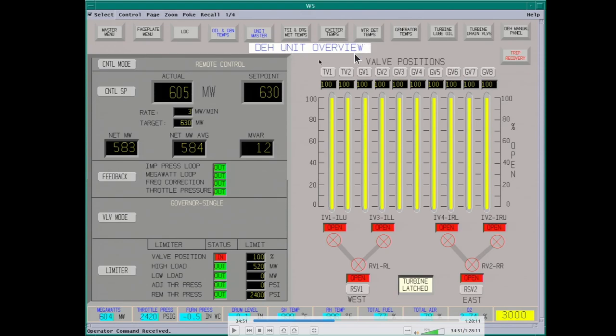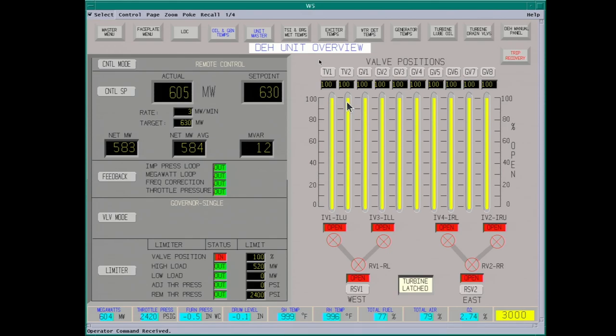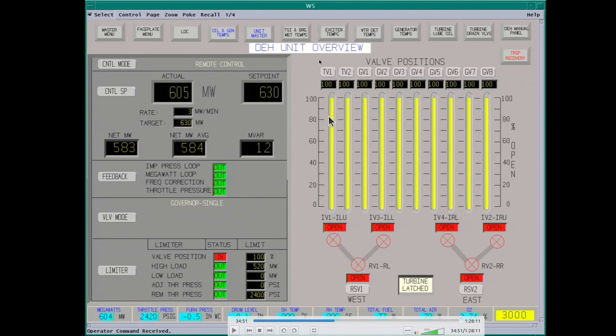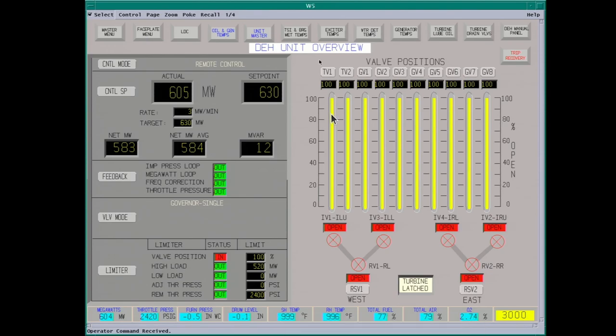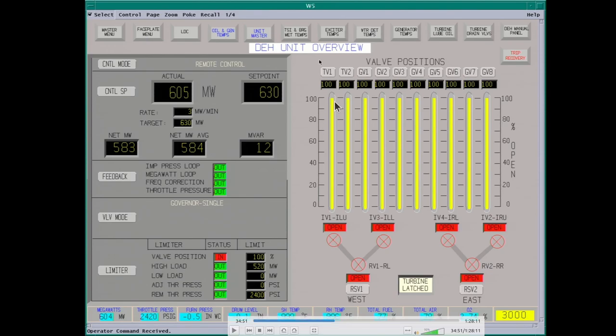This is the DEH unit overview screen — it shows the governor valve positions. There are eight governor valves, four on each side feeding the high-pressure turbine. The throttle valves that work with the governor valves are the trip valves. For plant startup, these are used to throttle the steam flow — there's a little pilot valve inside that opens to bring the turbine up to sync speed. At about 3,450 RPM you'll swap over to governor valves and do a valve transfer.